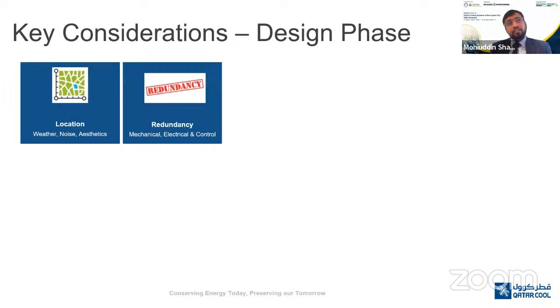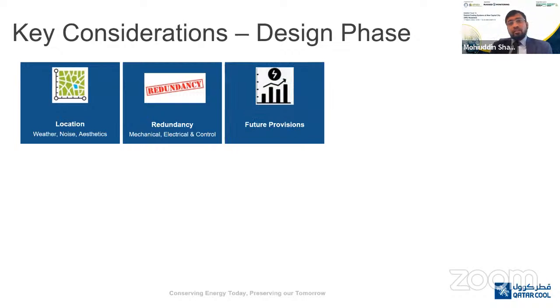The second aspect I would like to highlight is the redundancy. On the electrical side, N-1 at least should be considered on the incomers. Mechanically, yes, standby arrangements on chillers and pumps, although this has to be weighed against the cost as well, because the capital cost would be high. So depending on the criticality of the plant and the loads it is serving, decisions have to be made on the redundancy aspects. Future provisions: not all developments get built, or the city is built, at once. So as per the master plan, all the future provisions in terms of expanding the network and expanding the cooling capacity have to be appropriately provided.